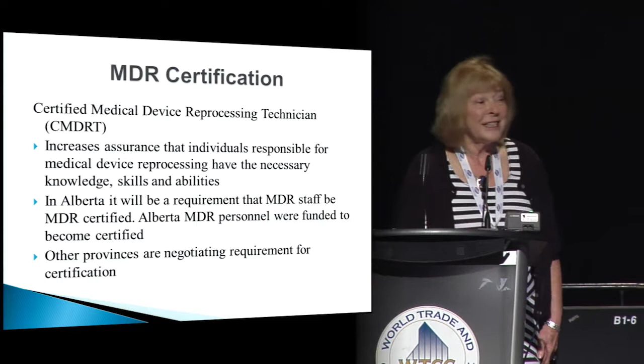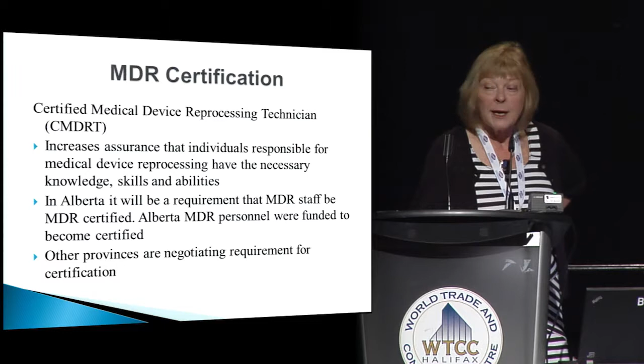And so Alberta is the first province to require certification for MDR staff. And they did fund the MDR staff to take their exams. And so other provinces are moving forward in that way as well. So it's important that the ICPs be involved in the purchase decisions of both the scopes and the AERs. And that's one reason I wanted you familiar with the standards. There are other standards too for you to work with, and so you can always contact Linda or myself or anybody else that's active with CSA if you are purchasing an AER, for instance, and you want more specifications and more information. But basically you need to make sure that the manufacturer has validated their equipment for the scopes that you either have in your inventory or are intending to purchase.